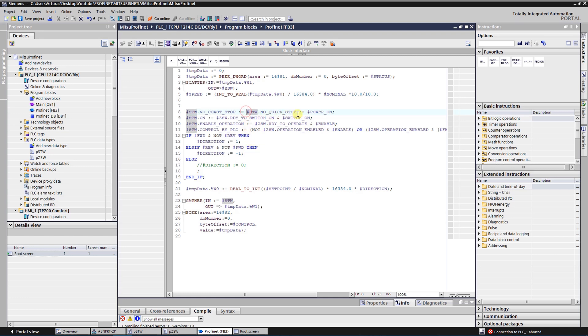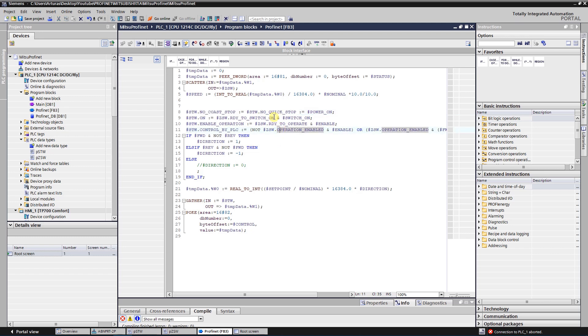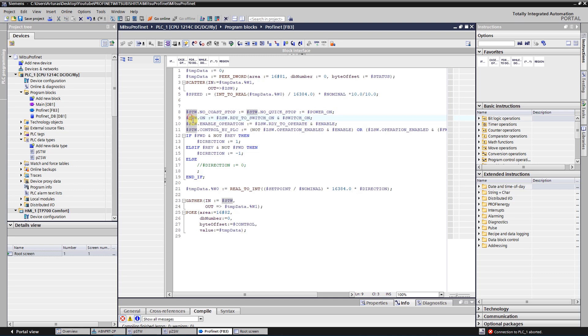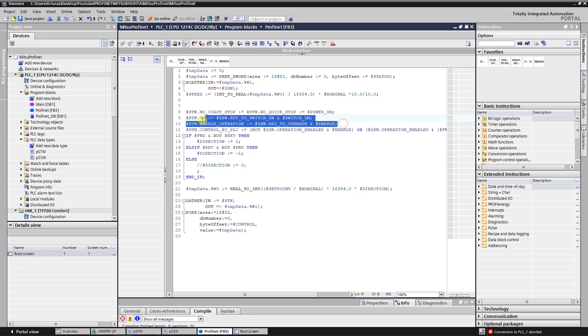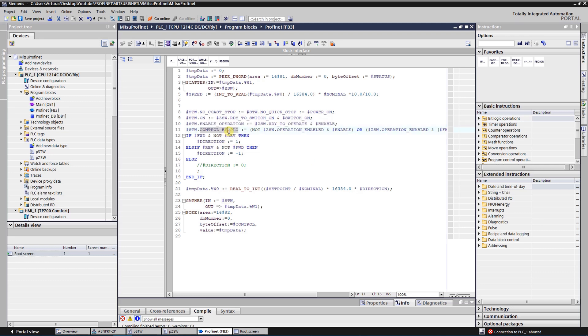First of all, I need to set the no coast stop and no quick stop. After that, if I get that VFD is ready to switch on, I do switch it on. After I send the bit switch on, I should get from the VFD that it is ready to operate. If it is so, I am enabling the operation.